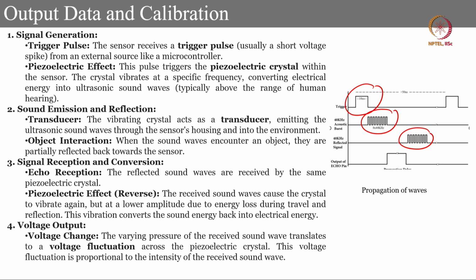The echo reception is where the reflected sounds are received by the same piezoelectric crystal, and the reverse piezoelectric effect is where the sound waves cause the crystal to vibrate again, but at a lower amplitude due to the loss of energy in travel and reflection. The vibration converts the sound energy back into electrical energy.